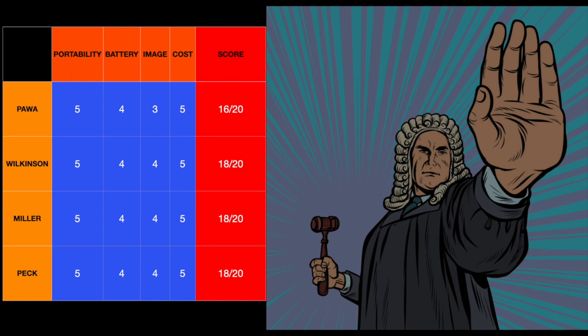So Marcus rated it 5, 4, 4 and 5. So that's 18, 18, 18 and 16 out of 20. All very good scores across the board. In fact, that equates to a total score of 17.5 out of 20 for the VScan Air, which I think is extremely good. And I think we all take our hats off to GE for what they've managed to achieve with this probe. It is wireless.